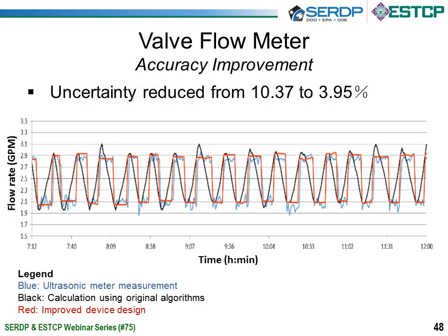This is an indication of the accuracy of the valve flow meter. You see flow rate here plotted against time for a period of, what's this? It's about a day, a little less than a day, it appears. And there are 3 lines shown. The 2 I want you to focus on are the blue line that represents the data from the ultrasonic flow meter, which can be viewed as the correct flow rate, and the red line, which represents the state of the virtual technology now. And these are the virtual sensed flow rates at the same time.